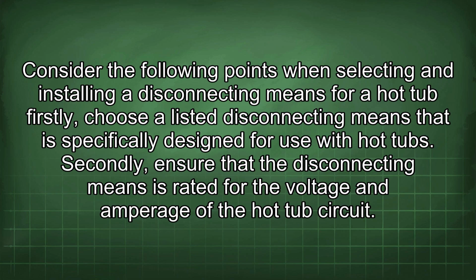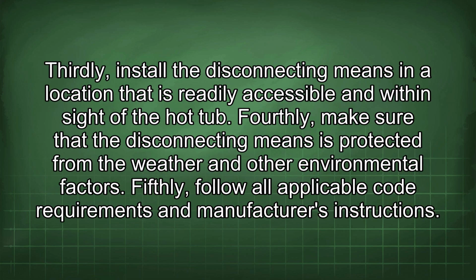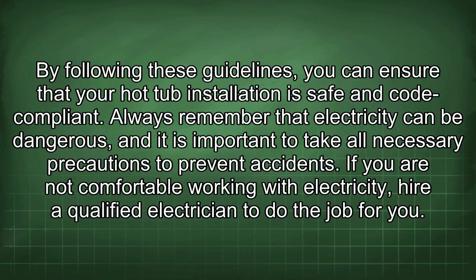Consider the following points when selecting and installing a disconnecting means for a hot tub. Firstly, choose a listed disconnecting means that is specifically designed for use with hot tubs. Secondly, ensure that the disconnecting means is rated for the voltage and amperage of the hot tub circuit. Thirdly, install the disconnecting means in a location that is readily accessible and within sight of the hot tub. Fourthly, make sure that the disconnecting means is protected from the weather and other environmental factors. Fifthly, follow all applicable code requirements and manufacturer's instructions. By following these guidelines, you can ensure that your hot tub installation is safe and code compliant.